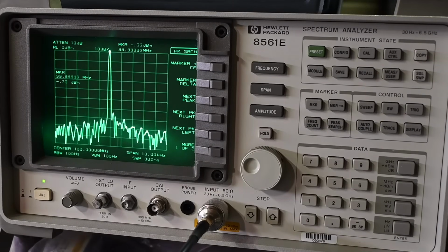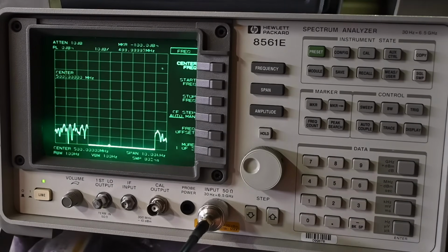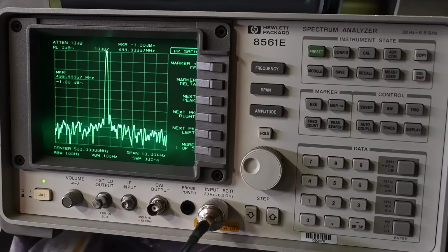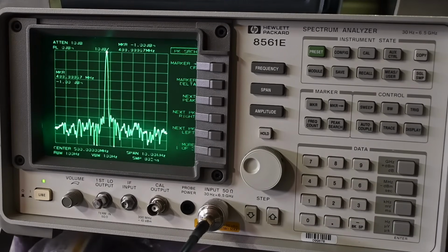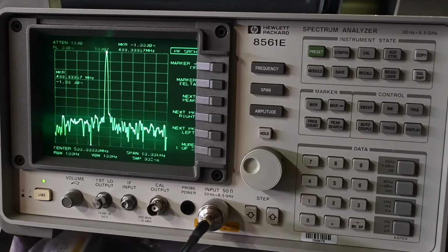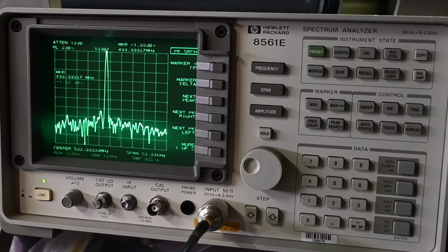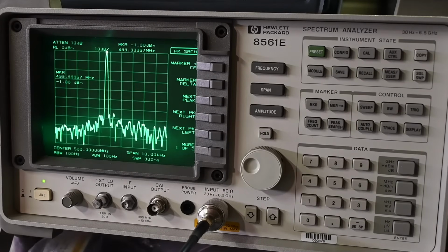But let's go over here. Let's try, let's say, 500 megahertz. Frequency, center frequency 500 megahertz. So again, the frequency is off just a little bit. I would expect that to sit a little bit closer to the 500. It's 499.99967. So, just off a little bit. Amplitude looks good, so it's sitting right at -1 dBm, but again, very reasonable for any loss that would be in 6 feet of this coax. It's connected right here, so I don't see any problems with that.